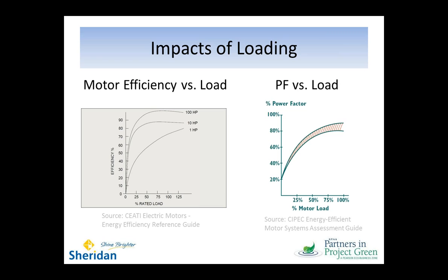The two curves here are going to help you understand some of the impacts of your control choices, in particular, significantly oversizing motors in relation to the application. What you can see from the efficiency curve is that the motor is going to be perfectly happy between 100% load, and even overload to some extent, down to about 40–50% loading. So if you have a very lightly loaded motor, its efficiency will be much lower than the efficiency of the motor running near its rated load.